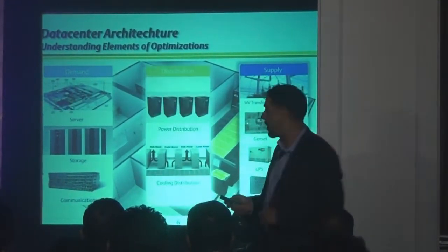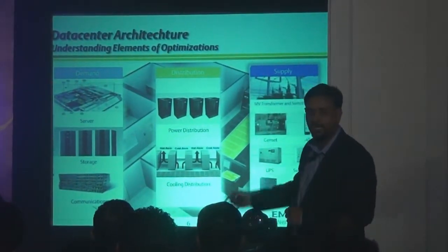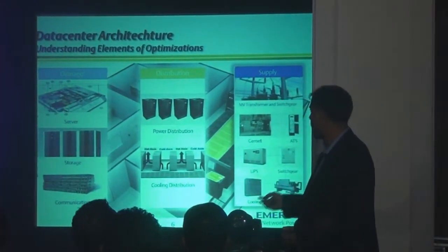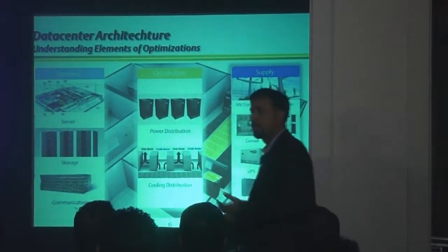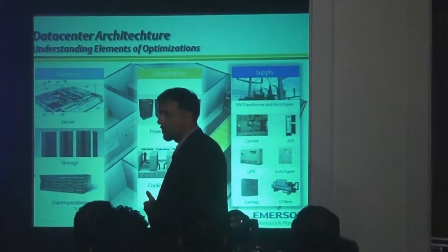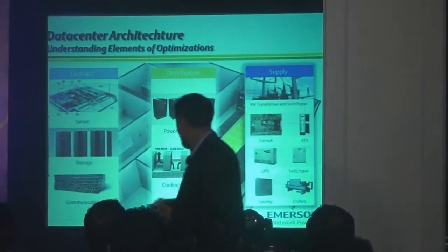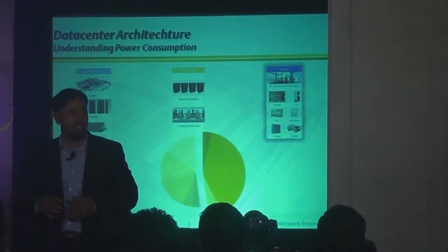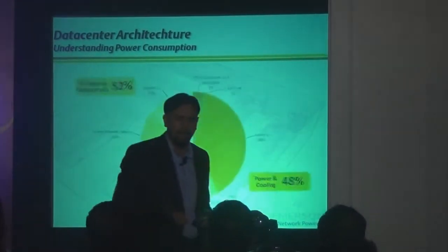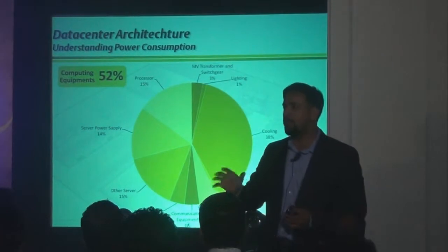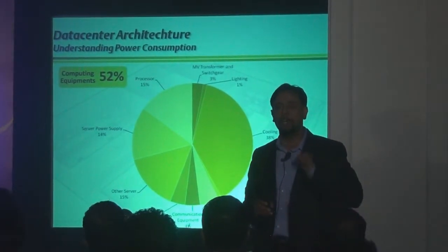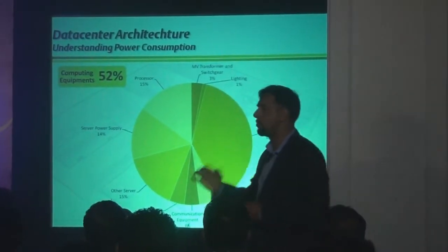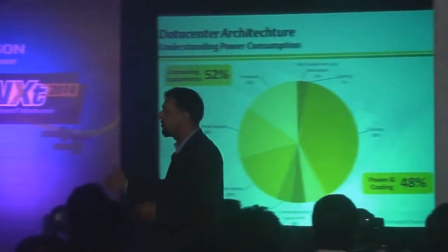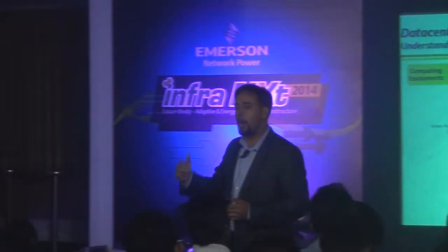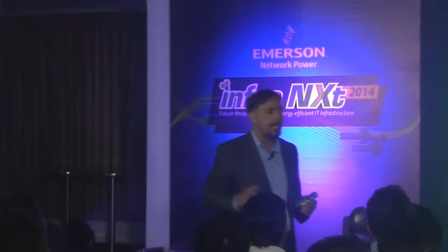For our understanding of how the data center layout is: you have the demand side, on the server side, then the distribution — power, cooling, or thermal distribution — and then you have the supply side from the genset. In a typical data center scenario, taking one example, about 50% of the power is distributed to the IT equipment, and the balance 50% is distributed between the other supporting infrastructure like thermal, power, and accessories like lighting or distribution.